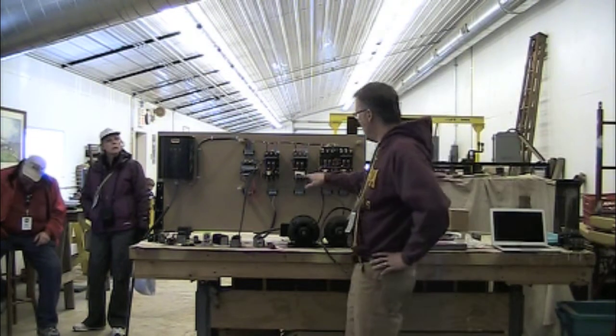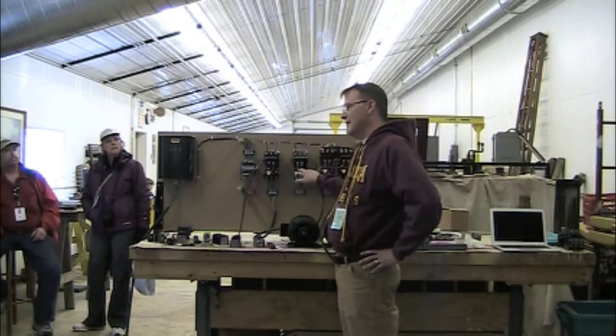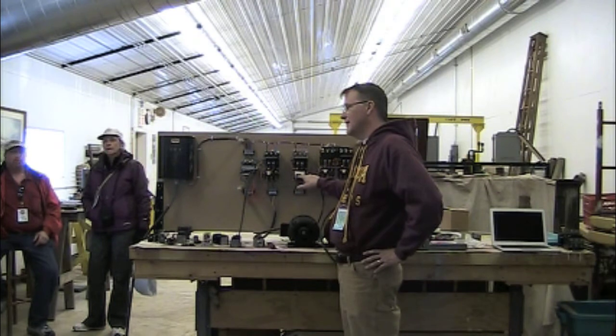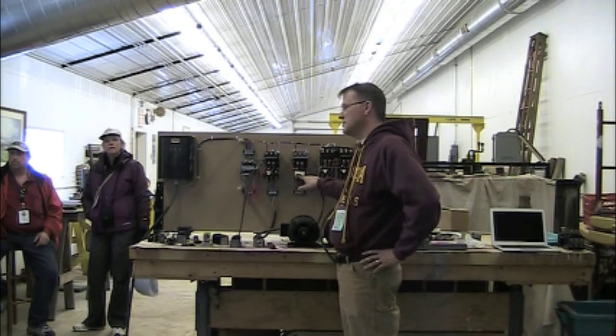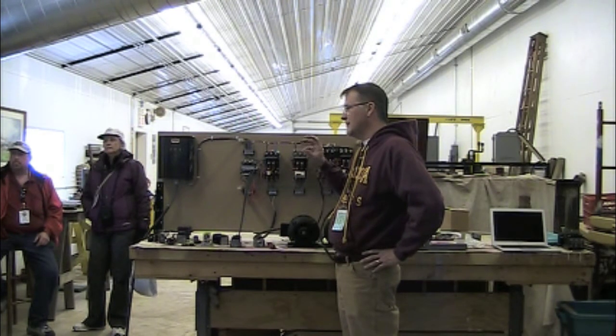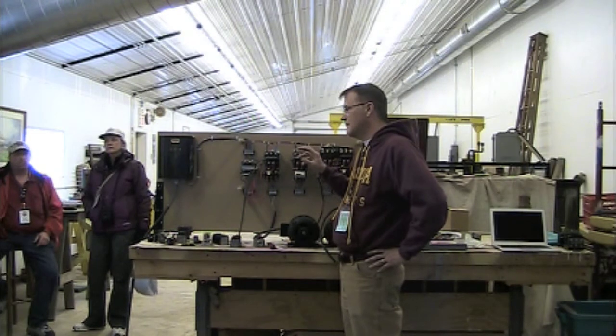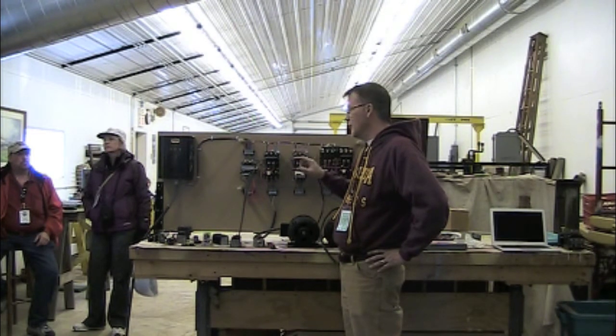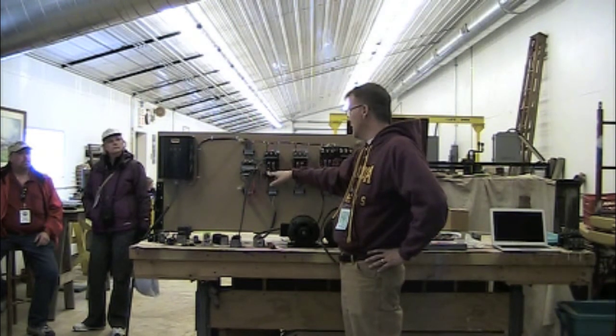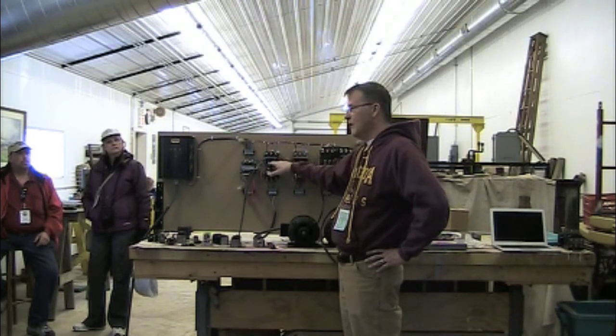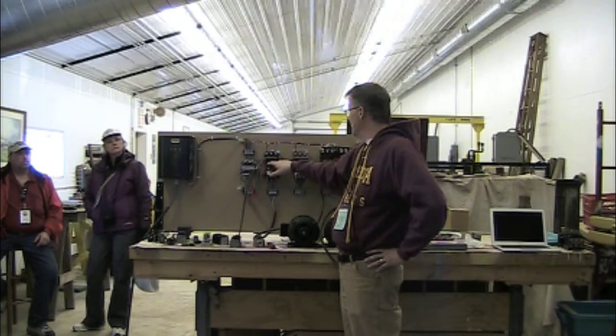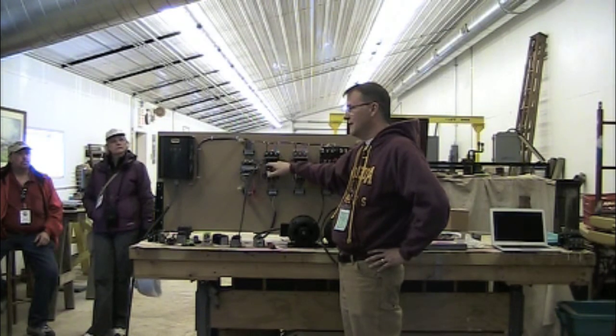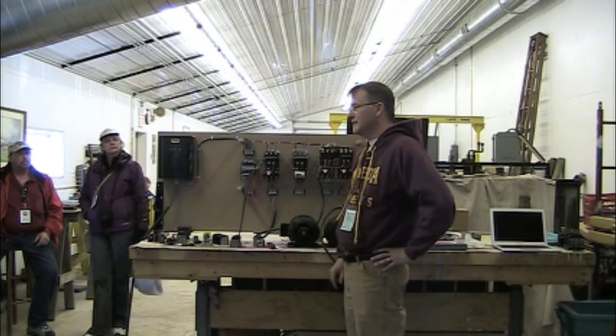They usually have multiple sets of NO and NC contacts, so that's why there'll be a bunch of numbers on them. Most IEC devices have multiple contacts, normally open and normally closed. The Allen Bradley ones like this, and a lot of the other brands, give you the one set you need, which is just the standard normally open contact set you need for a three-wire control circuit.